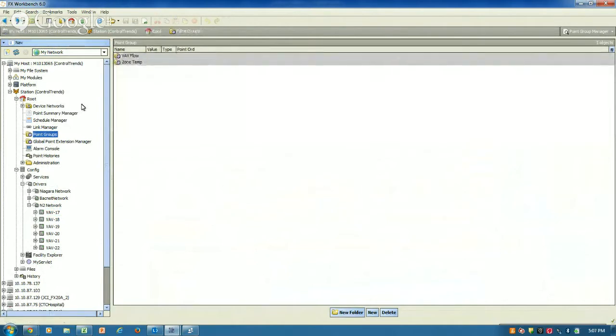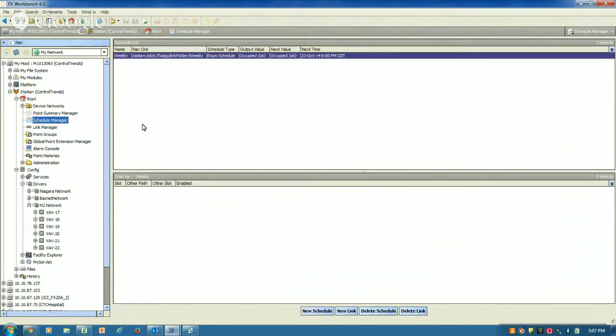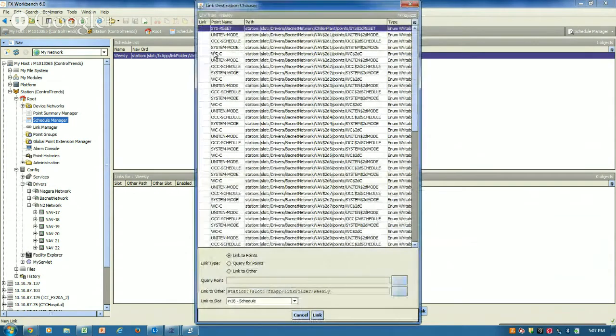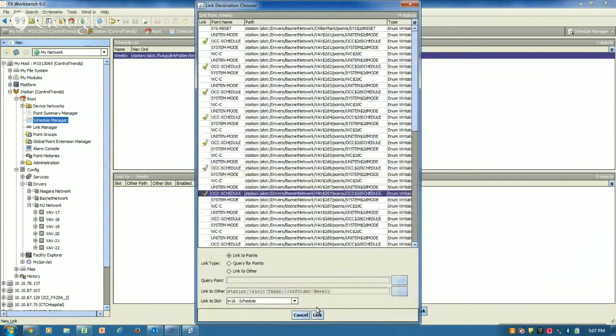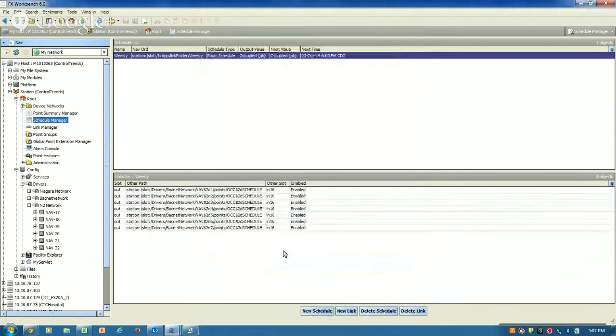So basically all I'd have to do, if I had the right controller application files loaded into the controllers and had it all set up, is go to my schedule manager, which we've engineered. You click on your schedule, do new link, and when you connect that one up, all you have to do is check the boxes for the Occ schedule - that's the point in Johnson Controls terms. Anytime this thing is occupied, it's going to send that occupied command to those points. You hit link, and now all those points are connected.